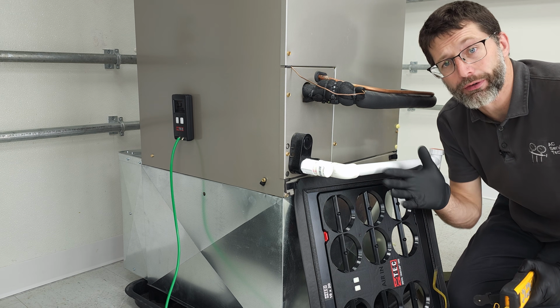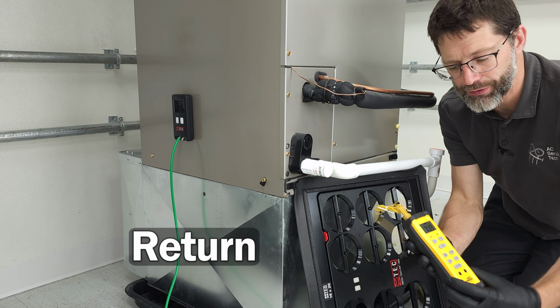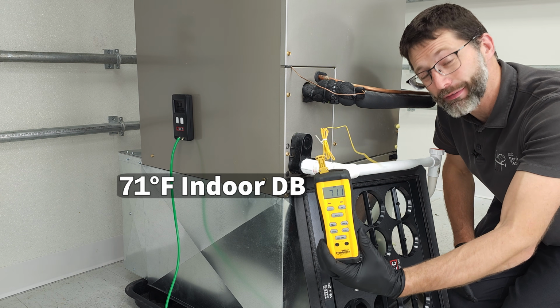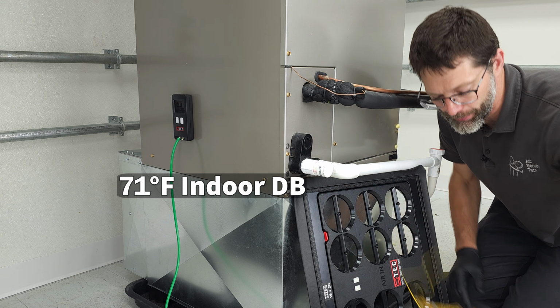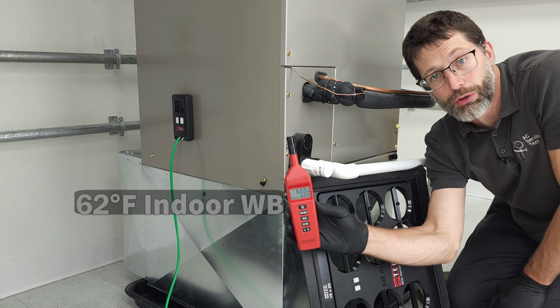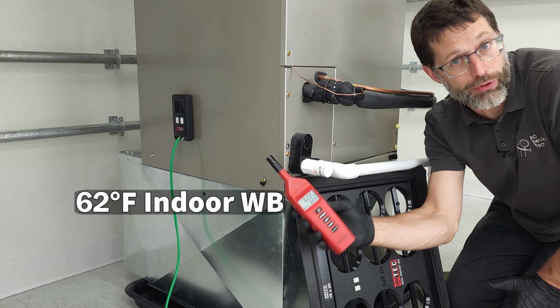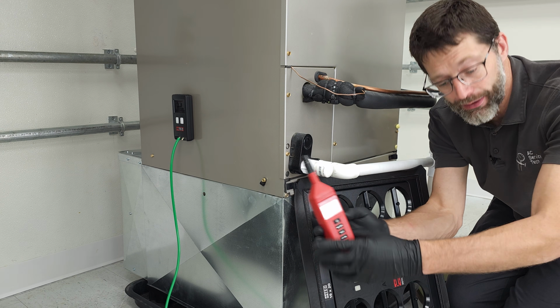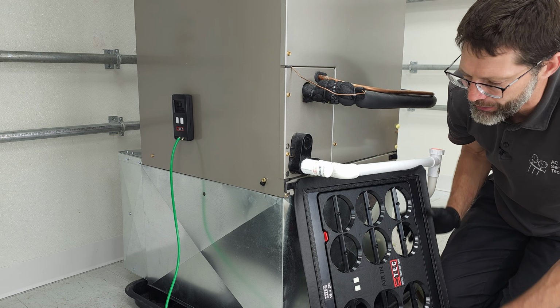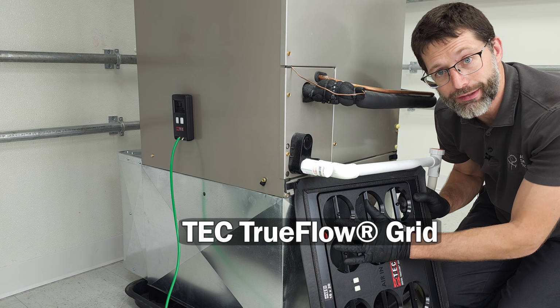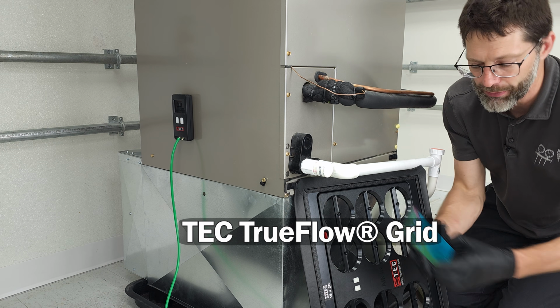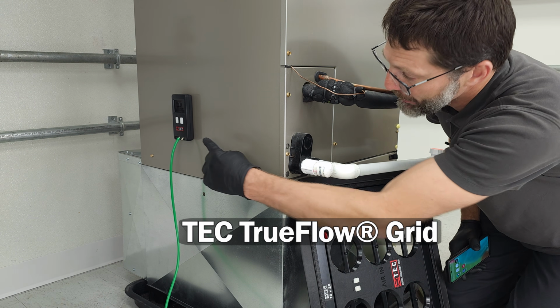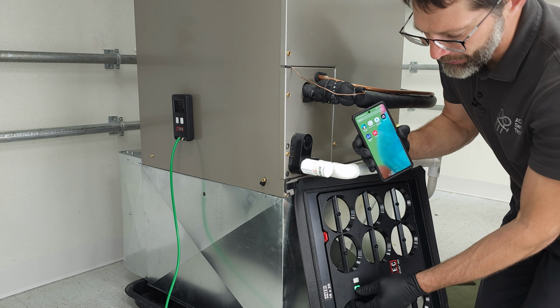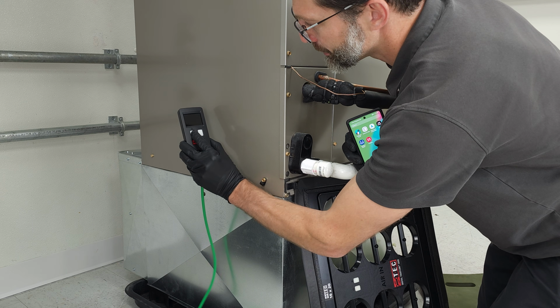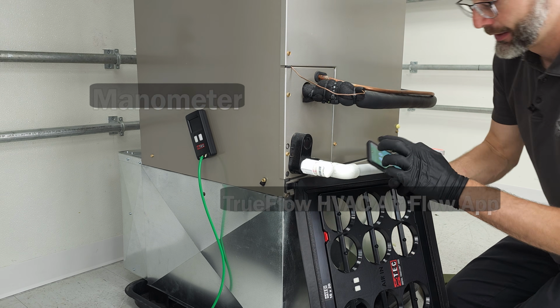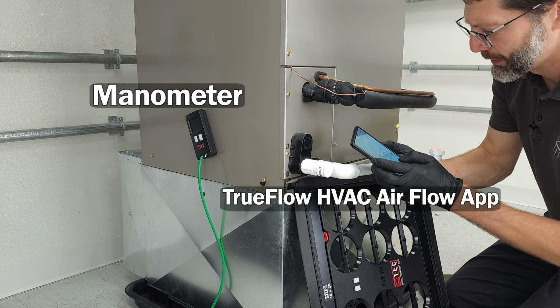Here we have our indoor air handler. This is the return, and just to give you a couple of reference points here, it's about 71 degrees as a dry bulb temperature inside the building. It's about 62 degrees as the indoor wet bulb temperature, as far as the amount of humidity in the air. And so we're going to be measuring the airflow with our TEC TrueFlow grid, and we're going to be using our app, and as well we're going to be using our manometer here. So we're going to turn this on. Turn this on. We're going to go to our app.